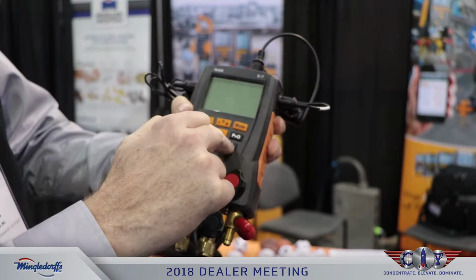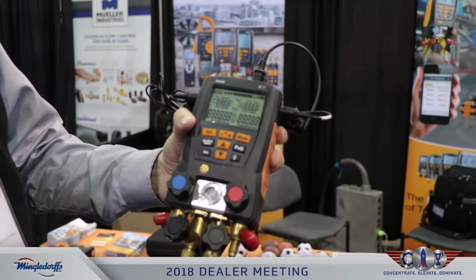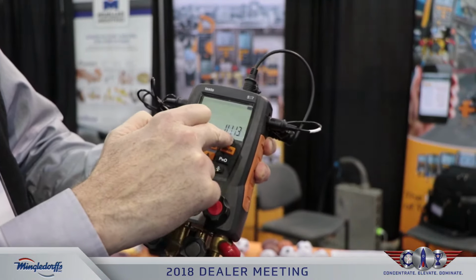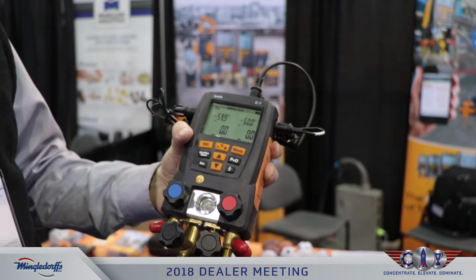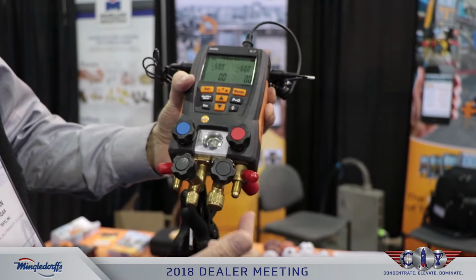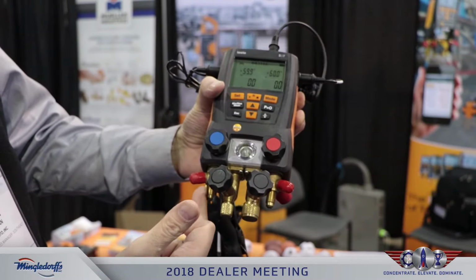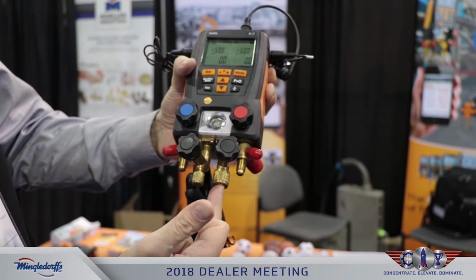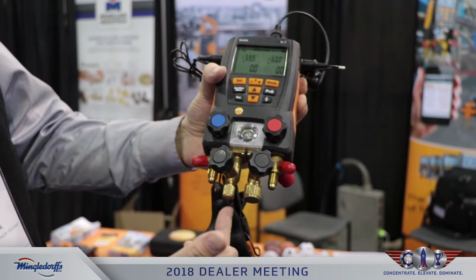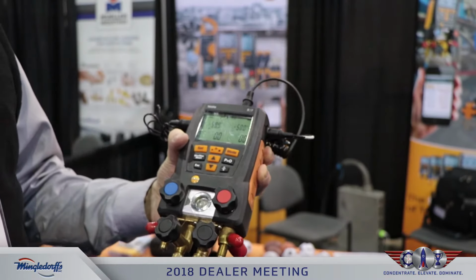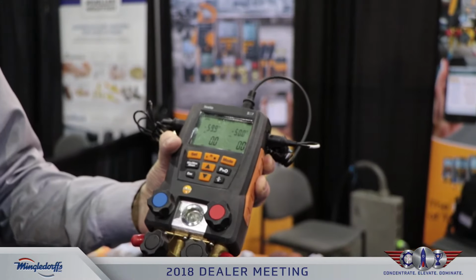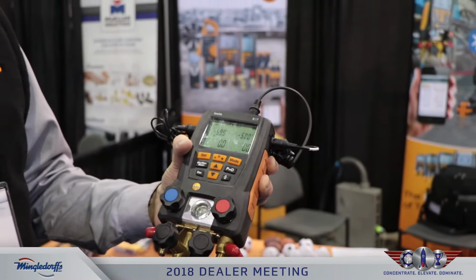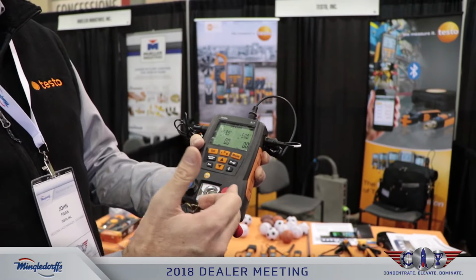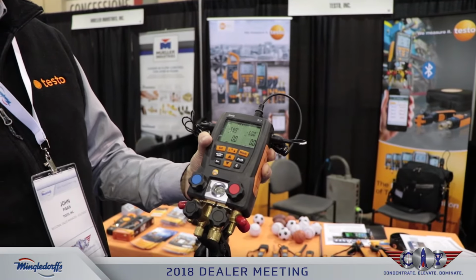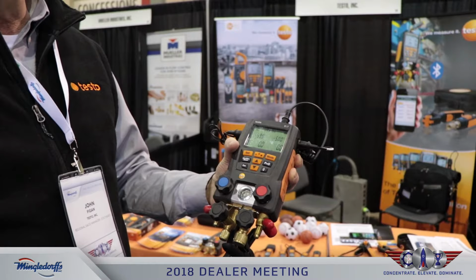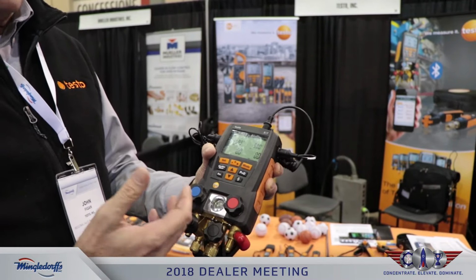We've got a number of refrigerants, about 60 refrigerants in the analyzer, and we're able to select the refrigerant. We're able to put the red hose on the red side, the blue hose on the blue side, and put the charging hose, black hose here, and your charging hose here. And we're able to calculate your superheat, your subcooling. We're able to measure your temperatures, your low and your high side temperatures, your low and your high side pressures for almost 60 or 70 different refrigerants. These are becoming very popular.